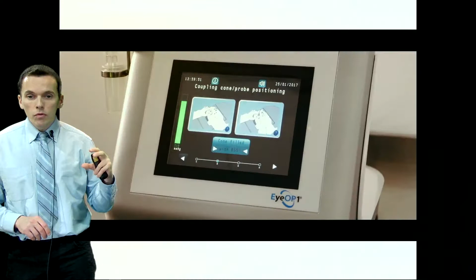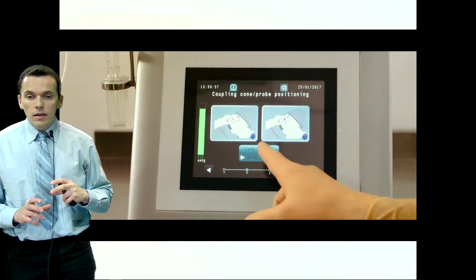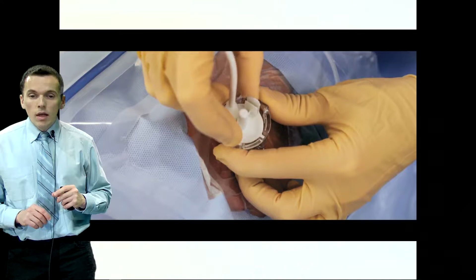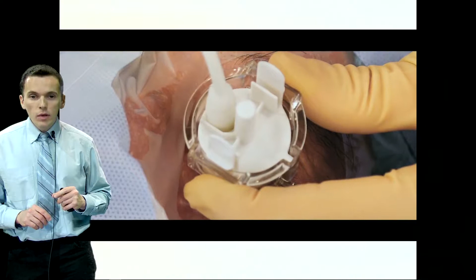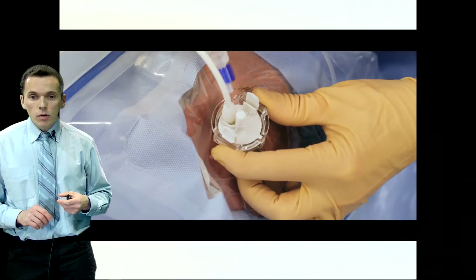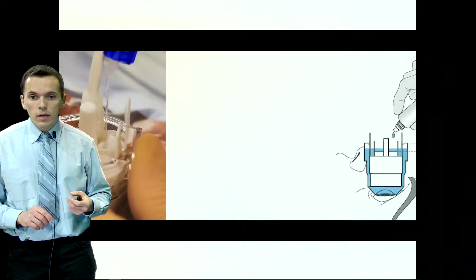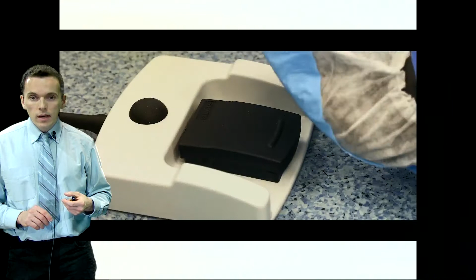We have a small vacuum system to fix the cone against the eye. It's a low pressure vacuum system, and it allows us to avoid any displacement during the treatment. So we insert the probe in the cone, as you can see. Then we fill the cone with water, of course for ultrasound propagation from the transducer through the ciliary body, through the target to be treated. So I fill the cone with saline water, as you can see here.